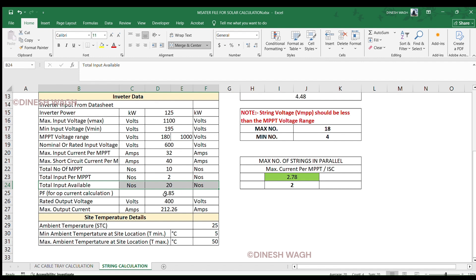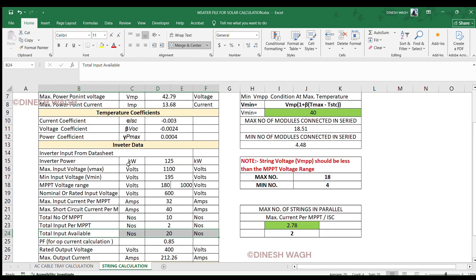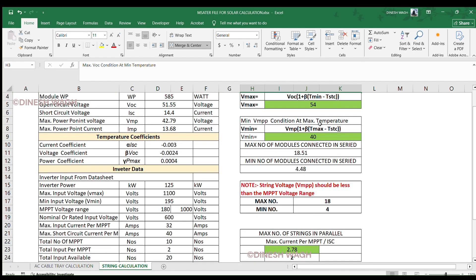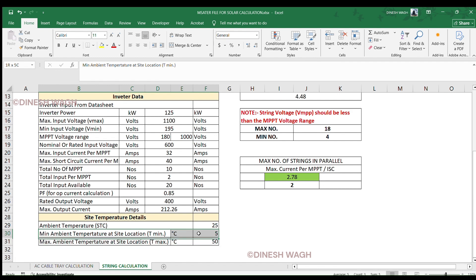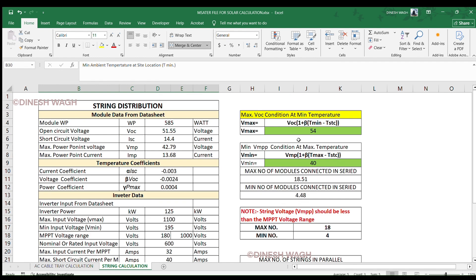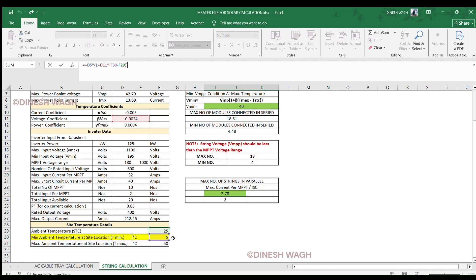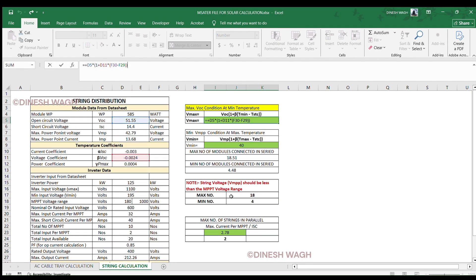In Part 4, we do the actual calculations — temperature-based voltage calculation. Let's calculate voltage changes due to temperature. V_max at low temperature: V_max = VOC × (1 + beta × (T_min − T_STC)). Executing: 51.55 × (1 + (−0.0024) × (5 − 25)) = 54 V. This gives us V_max of 54 V.